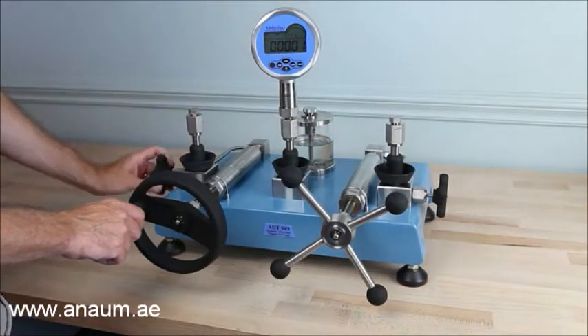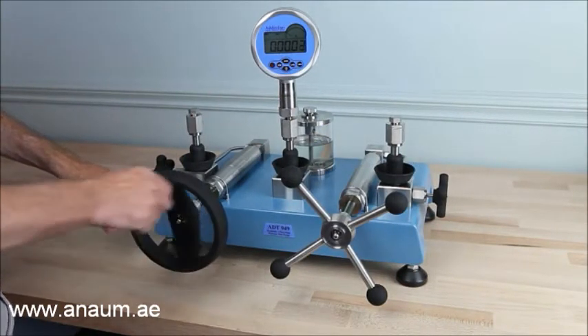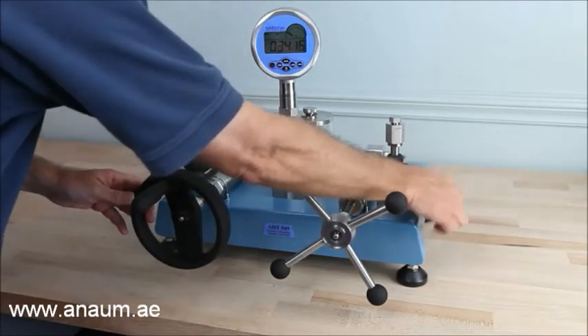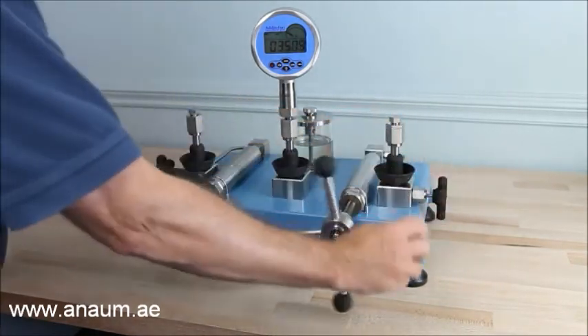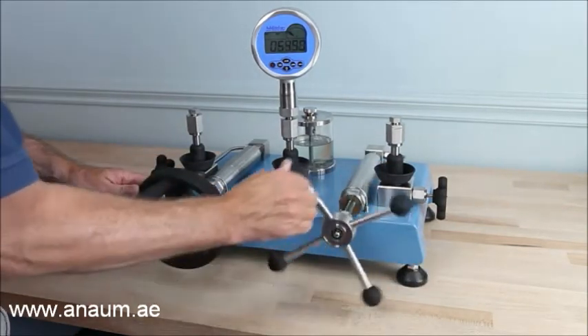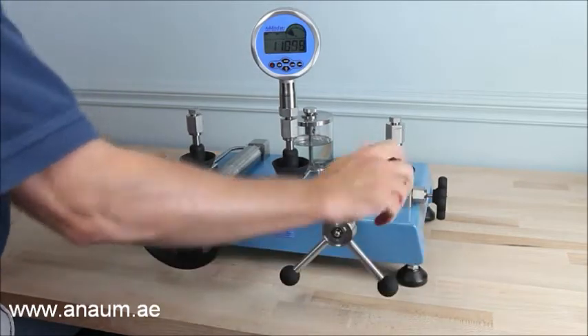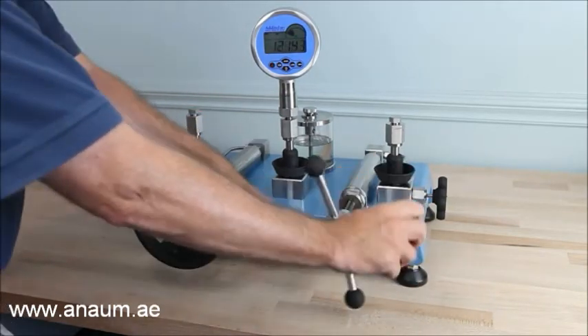To operate the pumps, first close the reservoir isolation valve and use the pre-pressurization side to generate up to a few thousand PSI. Then close the isolation valve and use the patented screw press to generate pressures to your test point. Unlike many scissor action pumps, pressures can be increased and decreased smoothly at all pressures. The 936 and 938 can generate 15,000 PSI in 30 seconds, and the 949 can generate 37,500 PSI in under one minute.